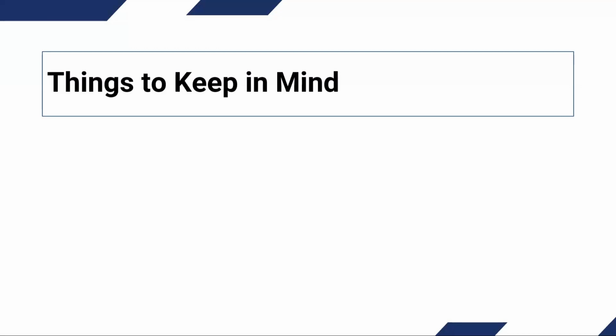Several things that are really important to keep in mind when you're dealing with projects is, I mentioned this multiple times, is the building positive? And quite frequently what we find is the building may not always be positive. A prime example is the kitchen hood may run from 10 o'clock until 1 o'clock. And it's frequent that when the kitchen hood comes on, some of these schools do become negative.